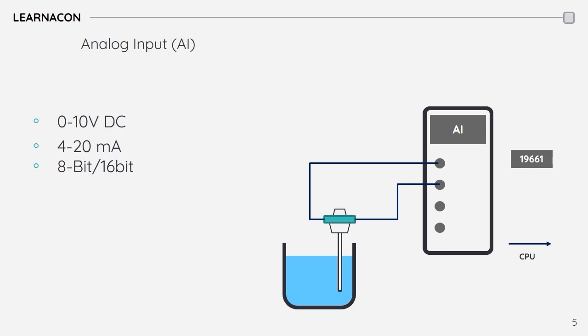Analog modules are offered with different precisions, which is defined in bits. The basic cards offer a 8-bit precision, and a more advanced card can go up to 16 bits. An analog input channel provides a raw value in form of number. To make this value meaningful, it needs to be scaled to the span of the respective instrument.